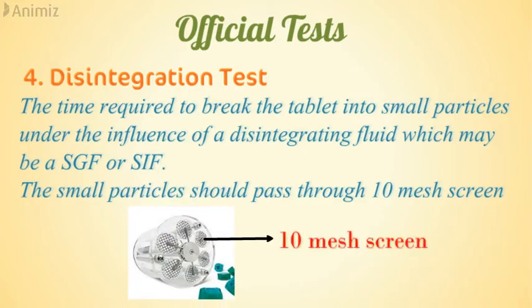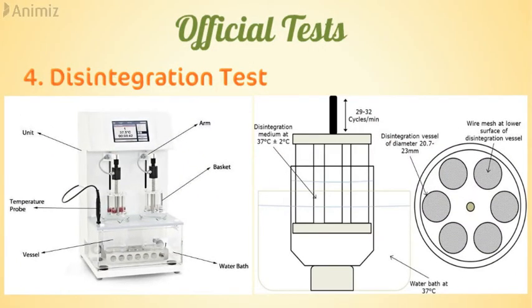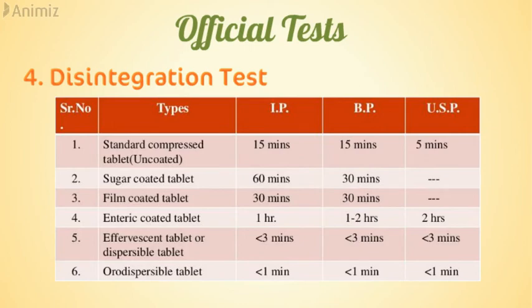The fourth official test is the disintegration test. Disintegration time is the time required to break the tablet into small particles under a disintegrating fluid — simulated gastric or intestinal fluid — with particles passing through a 10-mesh screen. The apparatus consists of a basket rack holding six open plastic tubes covered at the bottom with a 10-mesh screen, immersed in a bath held at 37°C in a one-liter beaker. The rack moves up and down at a specific rate.